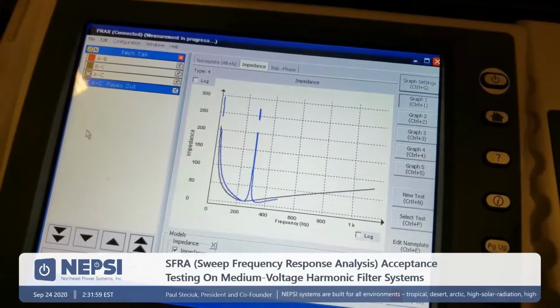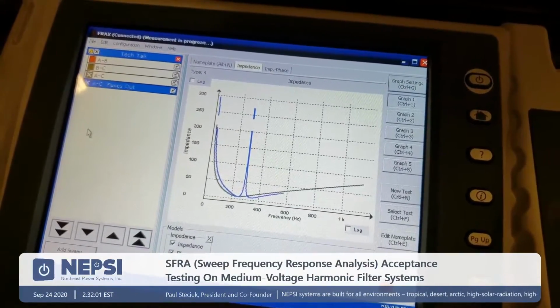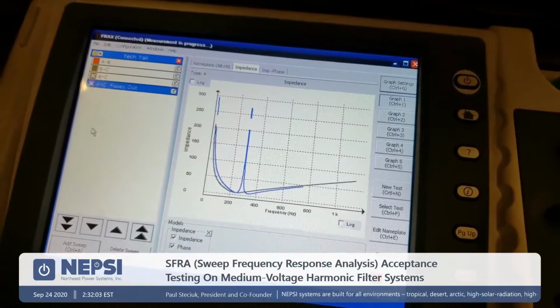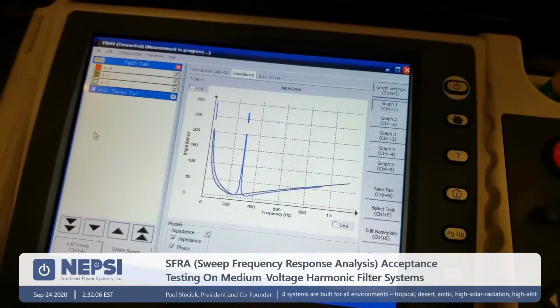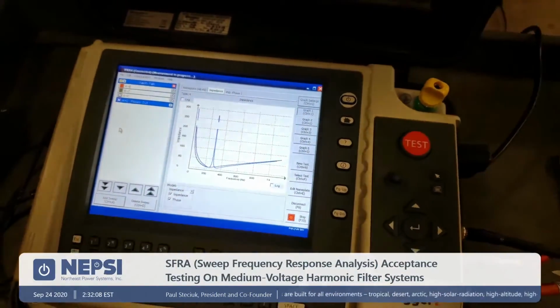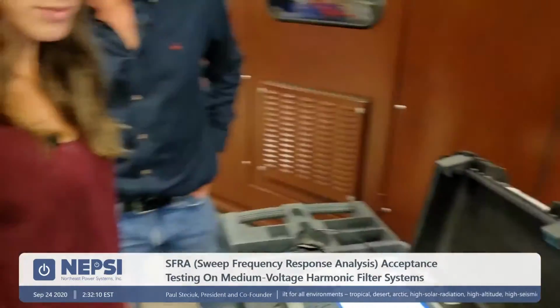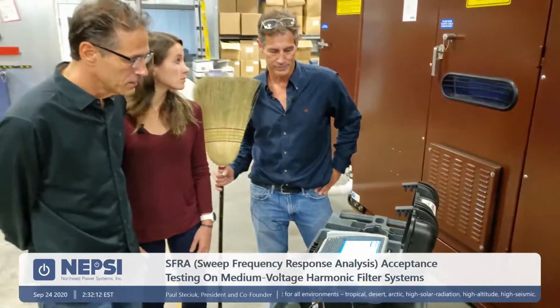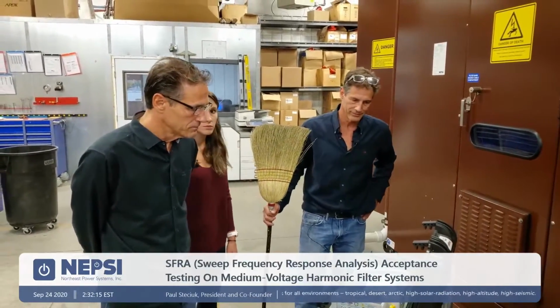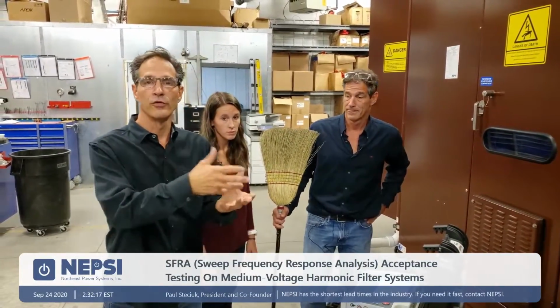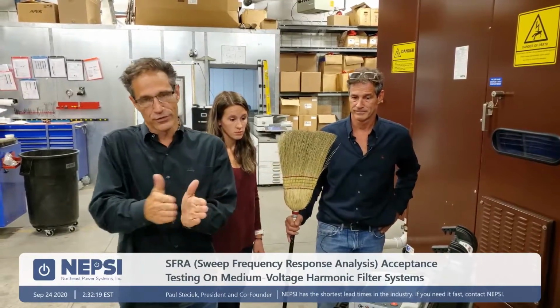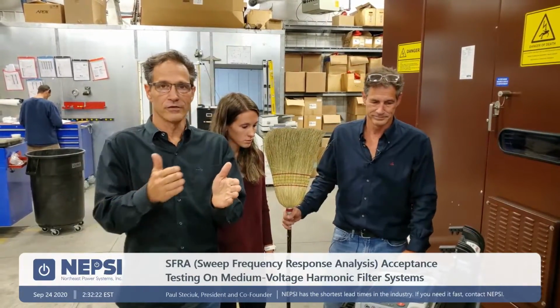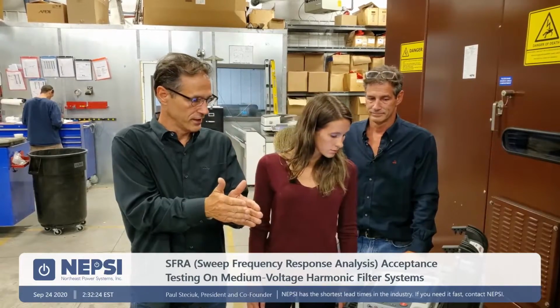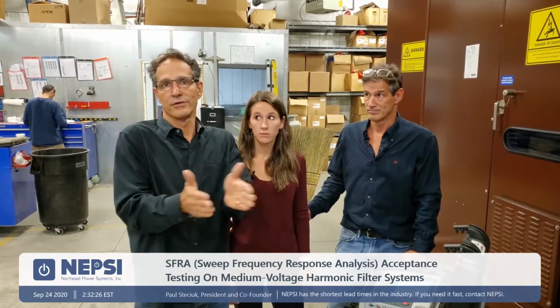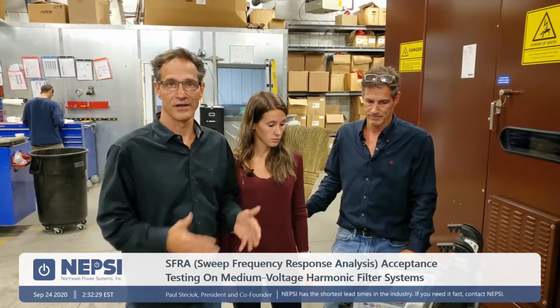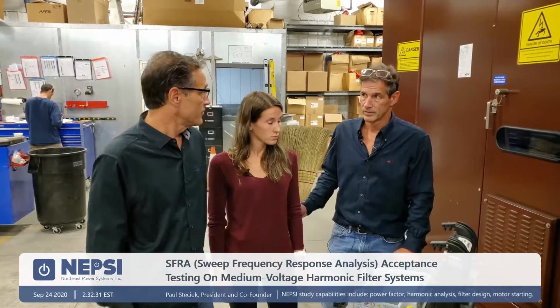Okay, well that is what you call an anti-resonant point. Paul can go into an explanation of that anti-resonant point, but that is a characteristic of a 5th, 7th filter arrangement. So Paul can go through that explanation. The tuning point, he removed some capacitors, the reactor's the same, he moved the tuning point up. So now we have basically a 5th tuned filter and another tuned filter. You have a resonance in between, and we're actually seeing that resonance here. I think that explains it.